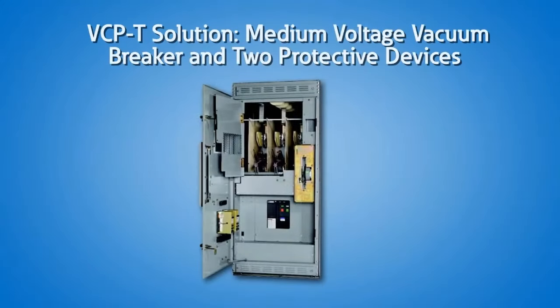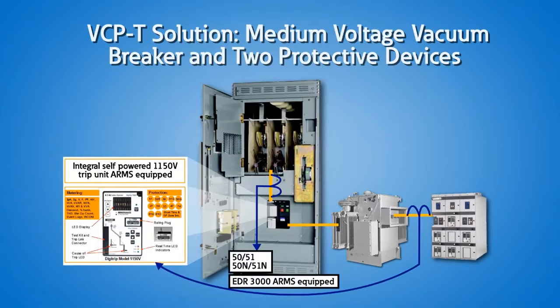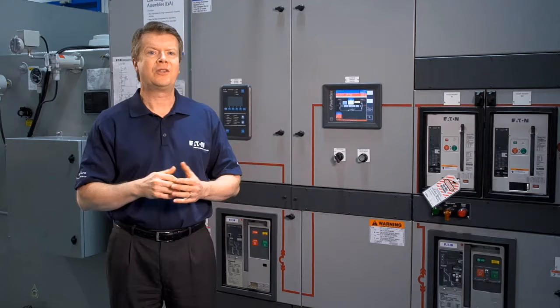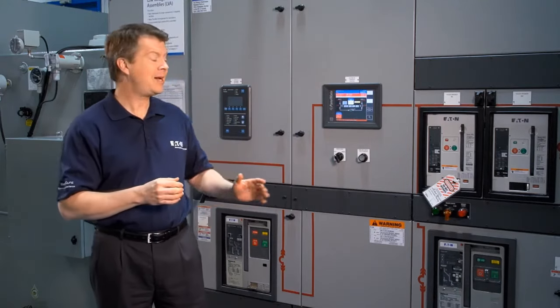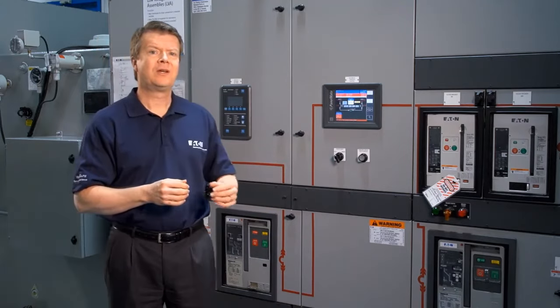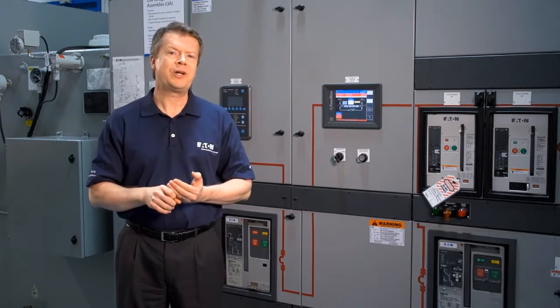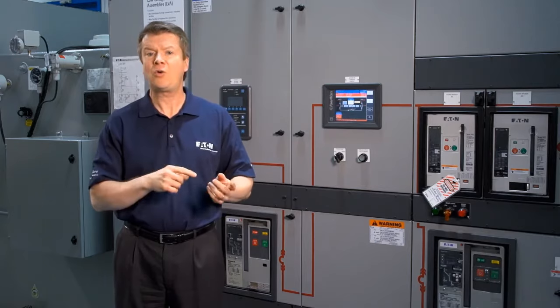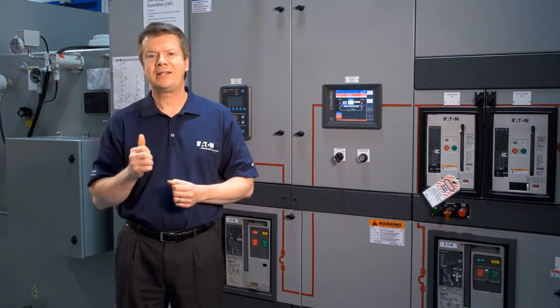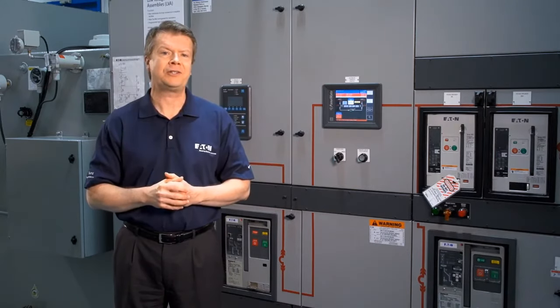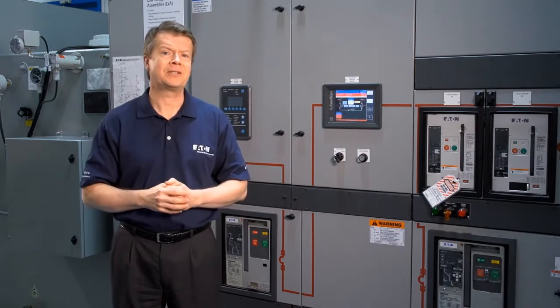Our VCP-T solution allows us to use a medium voltage vacuum breaker and 2 protective devices to detect faults in different zones around this transformer. The most difficult fault location being the line side of this main breaker. With this solution, this medium voltage breaker can selectively determine how quickly to clear a fault, significantly reducing the arc flash energy to well below 10 calories during maintenance conditions.